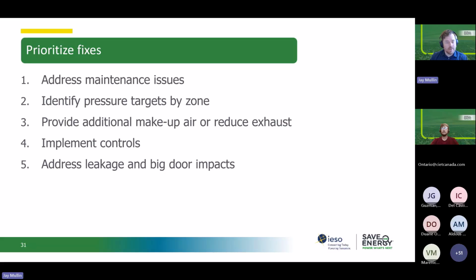That can be really useful, but an important thing to remember is making sure you have some guardrails on to account for things like loading bay door activity. If the doors are open, you don't want to exceed a threshold because of that impact. Also make sure you're not putting things at risk of freezing by bringing a whole lot of outdoor air in to address a negative pressure situation, or that you're still meeting minimum outdoor air requirements, even if that does result in positive pressure or things like that.